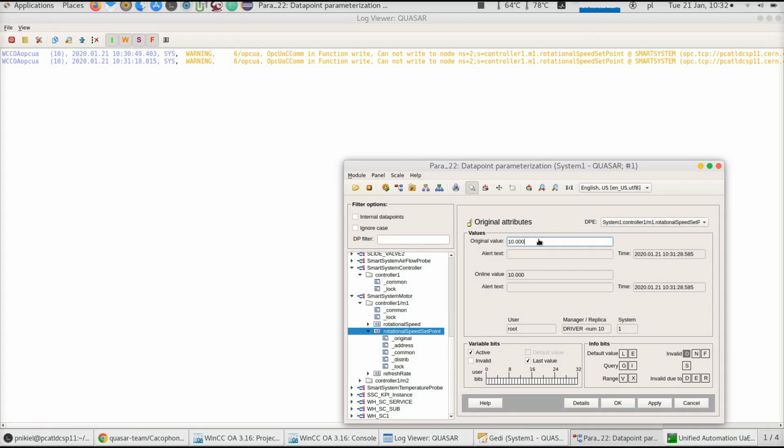This is all due to the way the WinCC OA architecture is. I know there might be something coming in the future which would be much better, but as of 2019 or 2020 there doesn't seem to be a right solution. So if you write your scripts using dpSet and dpGet, the same will of course happen. You will be able to do dpSet for any value, and then you will be stuck.